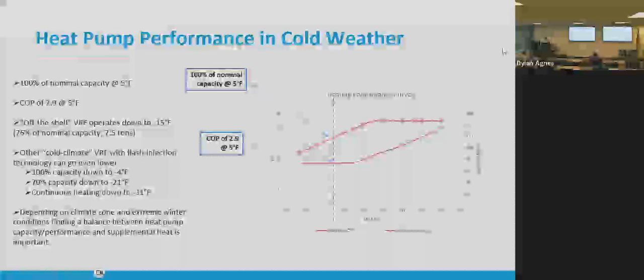And that heat pump in particular at that Bend site, right, when it starts getting into these -10s, the capacity does start to drop off. And of course, the actual heating load goes up. So we have a divergence here. But even at 5 degrees and -5 degrees, we still have almost nominal capacity. At 5 degrees, we're still at 100% of nominal capacity. At -5, we're at 90% of nominal capacity. So it's still there. And most of these heat pumps will keep running continuously down to -15. The cold climate ones that add vapor injection will go down to -31, and I think it's 50% capacity at that point, but it's still operating. So it's still not letting the building get too out of control.